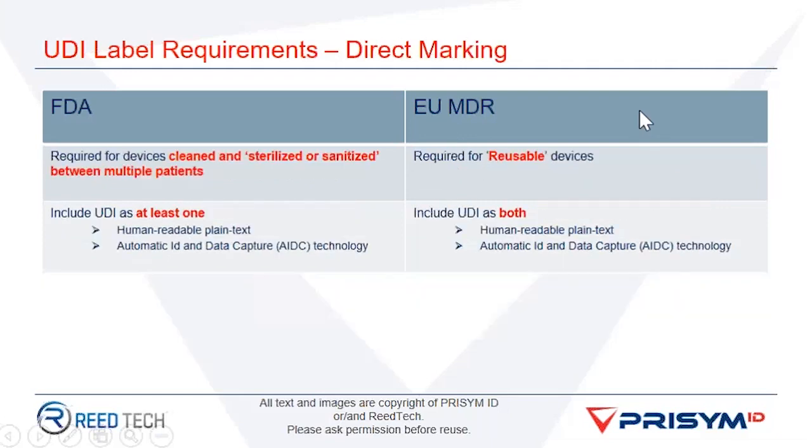There we go. Whether or not direct marking is required is very similar again, but worth confirming for your specific products. In the case of your processes, whether or not there are differences can be quite subtle. Both sets of regulations have recently provided clarifications on the wording that they use for this, with the FDA now stating that it's for devices cleaned, sterilized and sanitized between multiple patients, but the EU MDR has gone for the single reusable word. Both regulations have provided further clarification on what those statements actually mean in the real world.